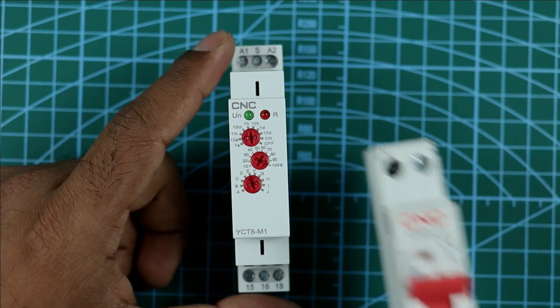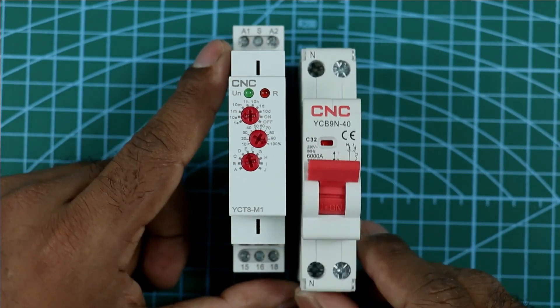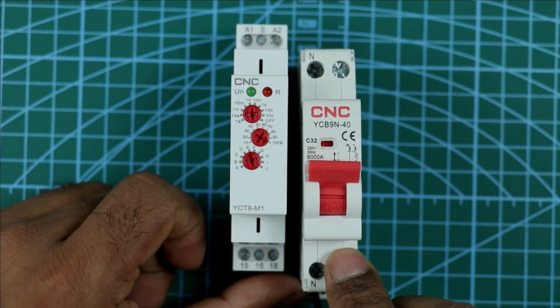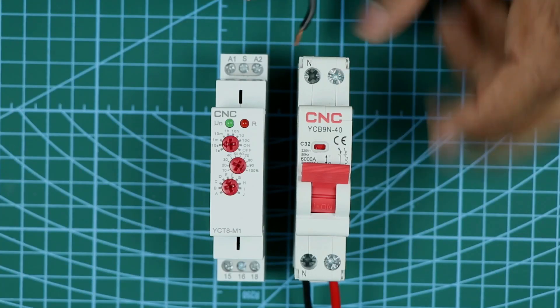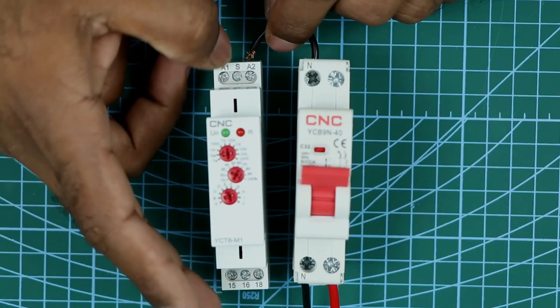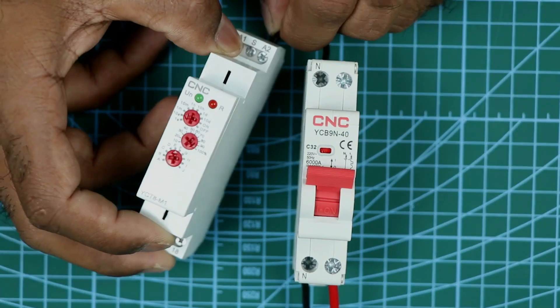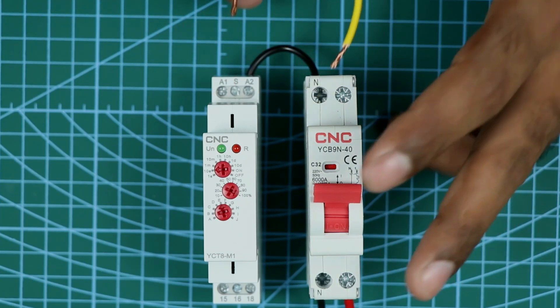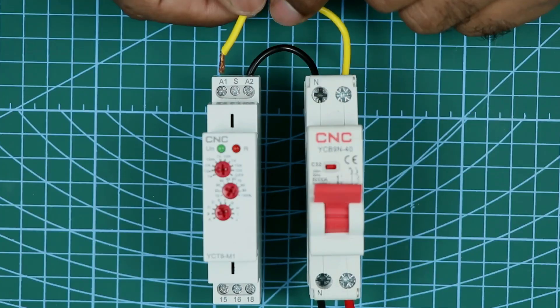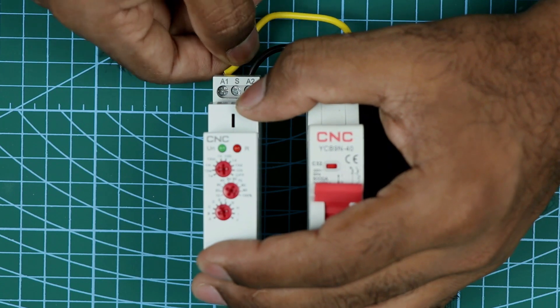For now, what I will do is I am taking this two-pole MCB, and through this MCB we will provide power supply to the timer. At the neutral terminal of MCB, connect one end of a wire. Other end of the wire is to be connected at A2 terminal of the timer. Now for phase supply, connect one end of wire with MCB and other end of the wire is to be connected with A1 terminal of timer.